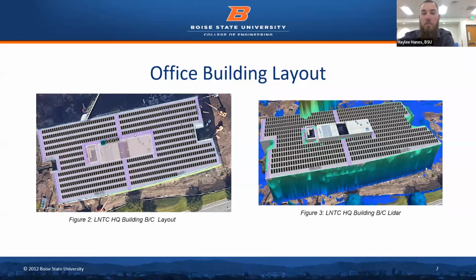Our team's design, what we did on all of them: we have all of our panels facing 165 degrees azimuth, and all the buildings have a tilt of about 28 degrees, with our open field having a single axis tracking system. All of our inverters are placed on the north side of a building and in shade, while the open field has its inverters underneath a shade. This is to help with overheating.